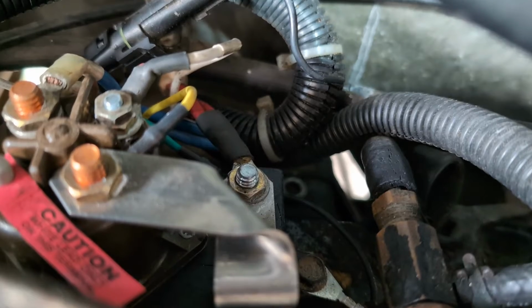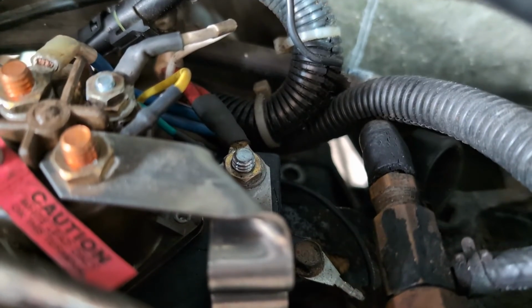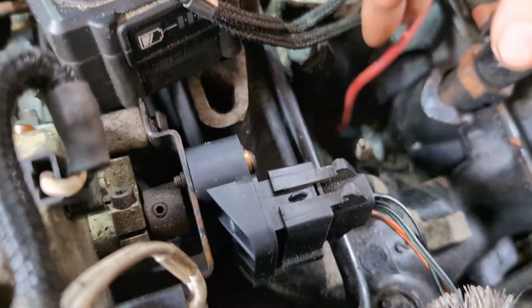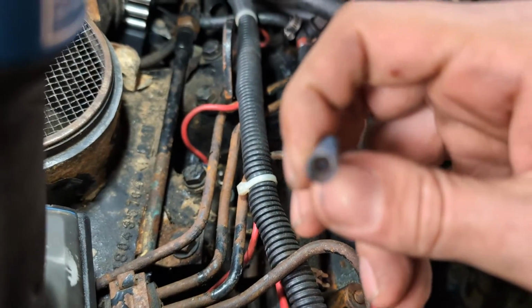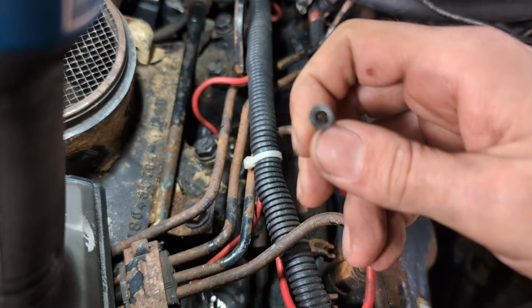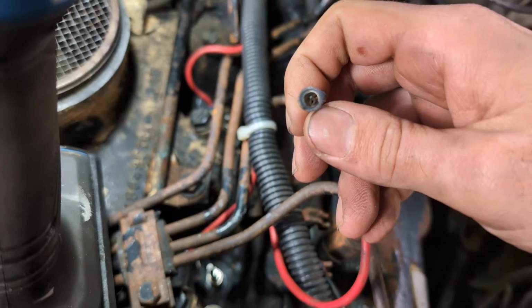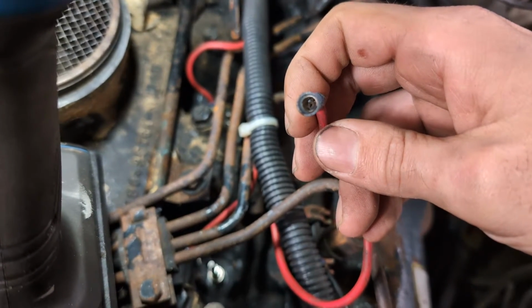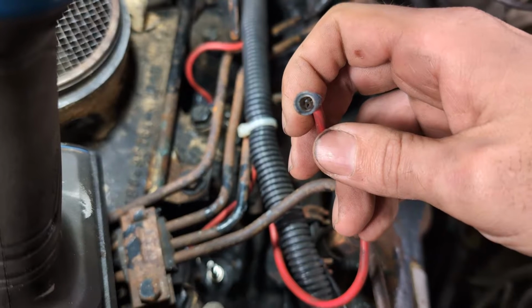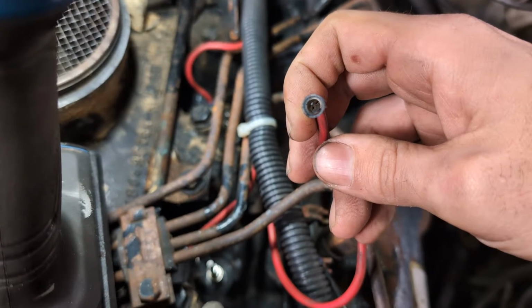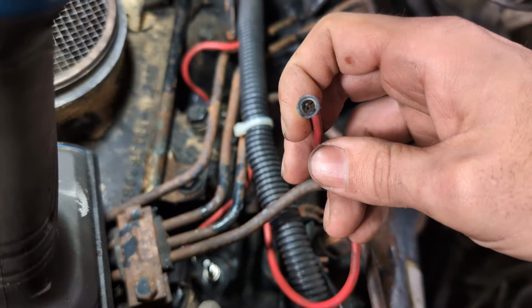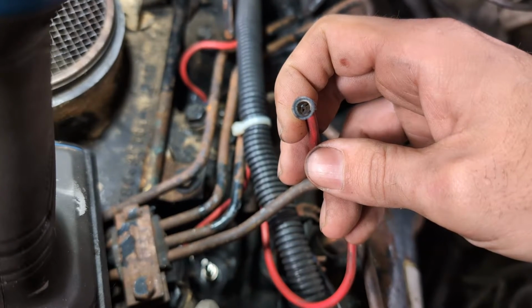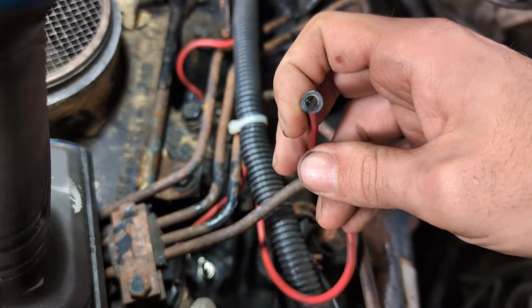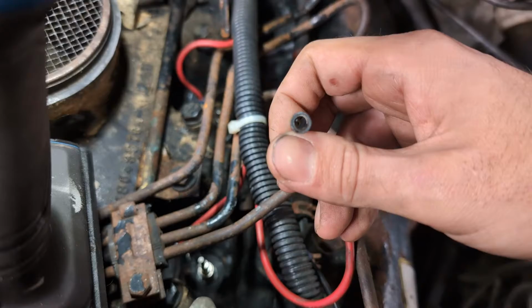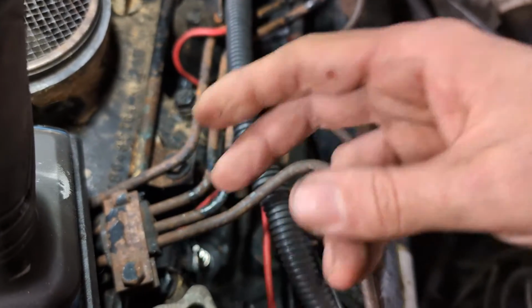You put one probe on this lug, and then put the other probe inside of your little connector hat here, and you're going to see the continuity. You should see something around 0.5 ohms. If you see anything drastically bigger than that, you probably have a continuity issue, a bad connection somewhere.